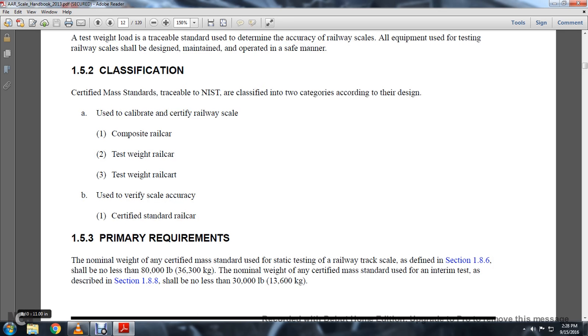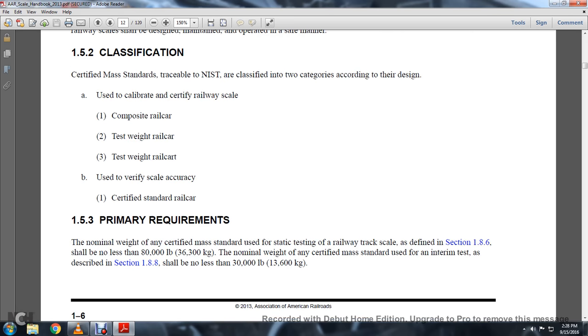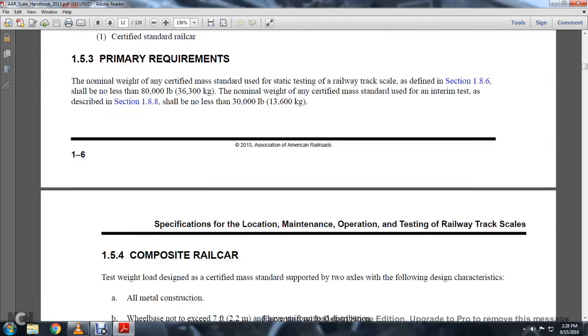1-5-3: Primary Requirements. The nominal weight of the Certified Mass Standard for static testing of a railway track scale as defined in Section 1-8-6 shall not be less than 80,000 pounds. The nominal weight of any Certified Mass Standard used in an interim test as described in Section 1-8-8 shall not be less than 30,000 pounds.